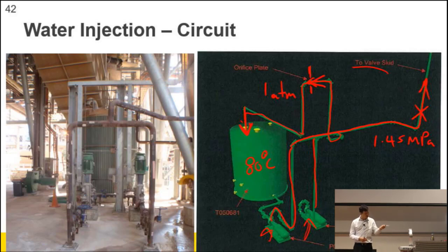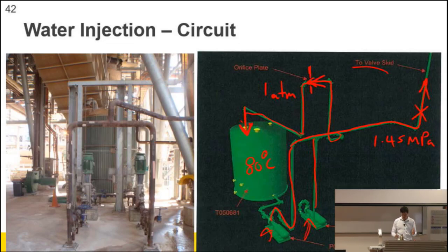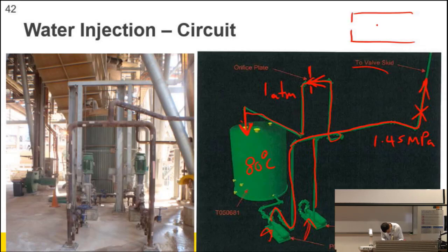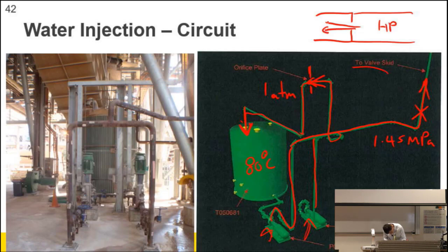It doesn't explode, but it's like exploding. Cool, all right, the process is called cavitation, right? And it's a process of boiling. So if you've got high pressure liquid, so this is high pressure, it goes through there, okay? It sprays through here and creates low pressure vortices in these corners, okay? And we know at low pressures, something that's 80 degrees C will boil, okay?